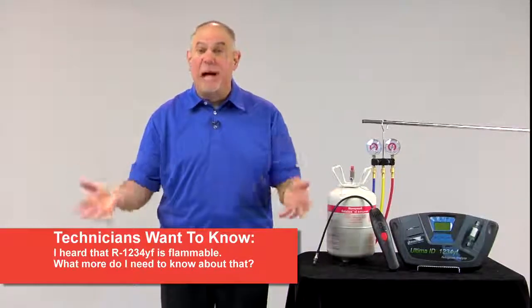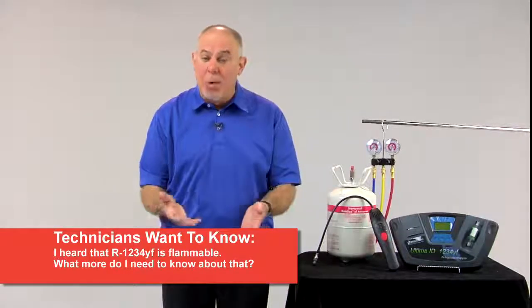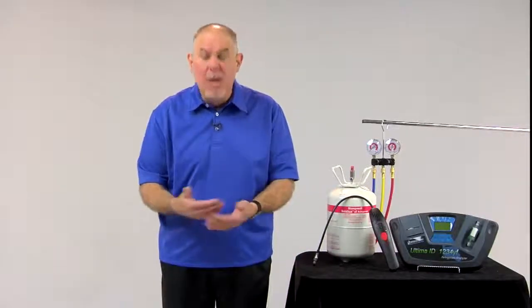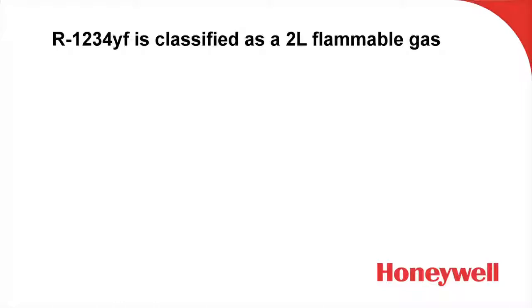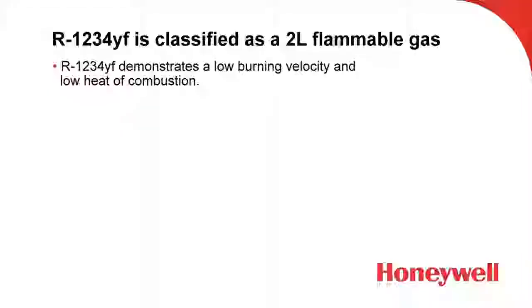You may have heard that it is flammable. Well, yes, it is flammable, but it's mildly flammable, meaning that it could ignite if it would come in contact with, say, for instance, an open flame or an extremely hot surface. It's classified by ASHRAE as a 2L flammable gas. That means that the gas, the refrigerant itself, has low burning velocity and low heat of combustion if it were to ignite. Let's talk about that low burning velocity in a little bit more detail.